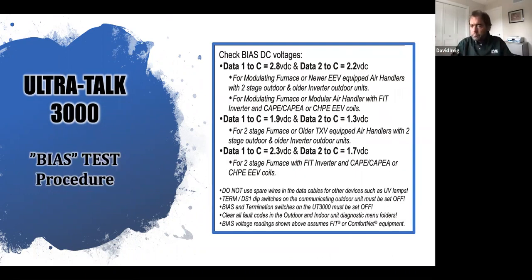Part of the other setup here is we highly recommend that you do a bias test upon finishing your installation. What is a bias test? Well, you've got to understand we're dealing with data communication here. It's very, very important that we maintain communication. So what you're testing for is that you have properly connected to the terminal strip, so you've got a secure, tight fitting if you've used any wire nuts. This will ensure that if you're getting these readings, you have done a good job. You can pat yourself on the back for doing a good job of wiring, and you're going to get proper communication. Improper communication will obviously give you sporadic operation and nuisance calls from the homeowner, nuisance operations.